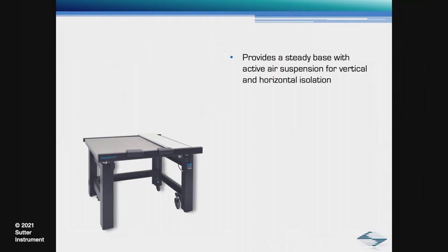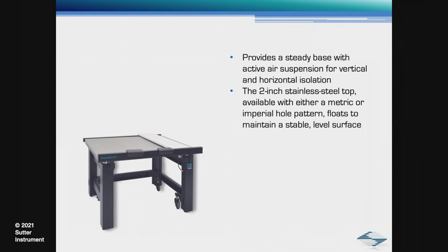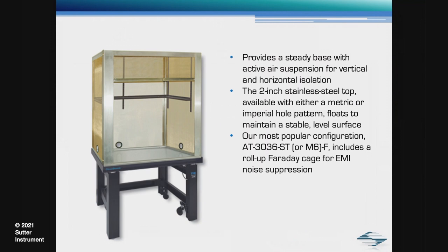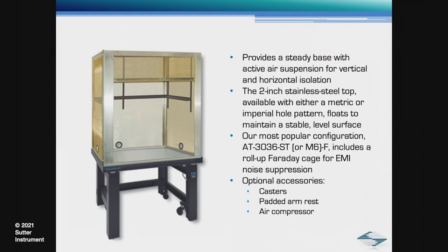Electrophysiological recordings are highly susceptible to environmental factors that introduce noise to the signals. Predominant noise sources are mechanical vibration and electromagnetic interference. Sutter offers a series of vibration isolation tables and accessories from TMC Vibration Control. Each table provides a steady base with active air suspension for vertical and horizontal isolation. Optional accessories include casters for making it easier to move the table, padded armrest, and air compressor for labs without house air.